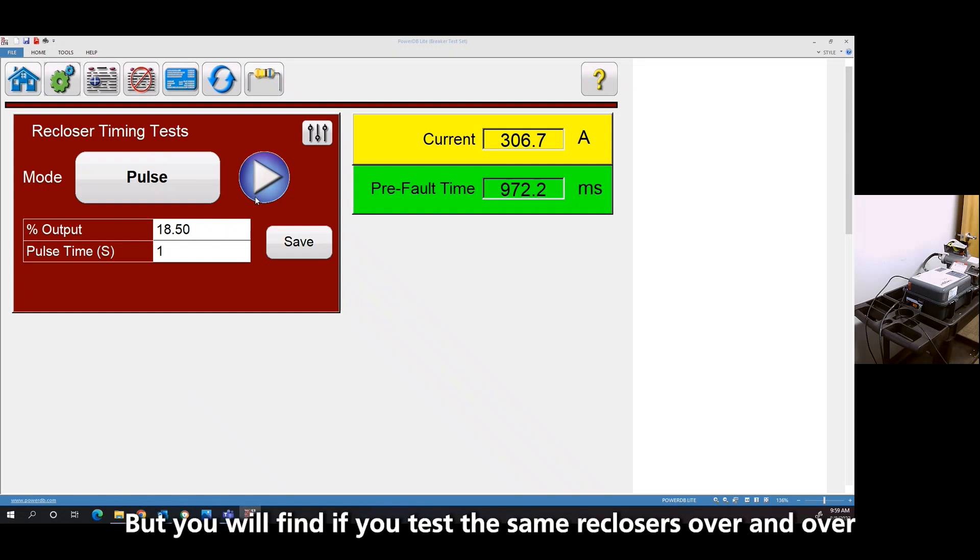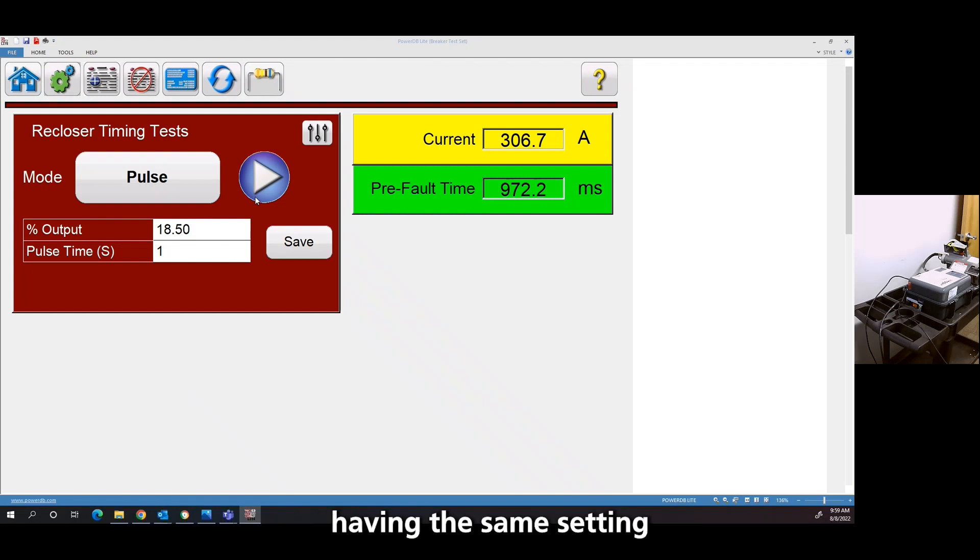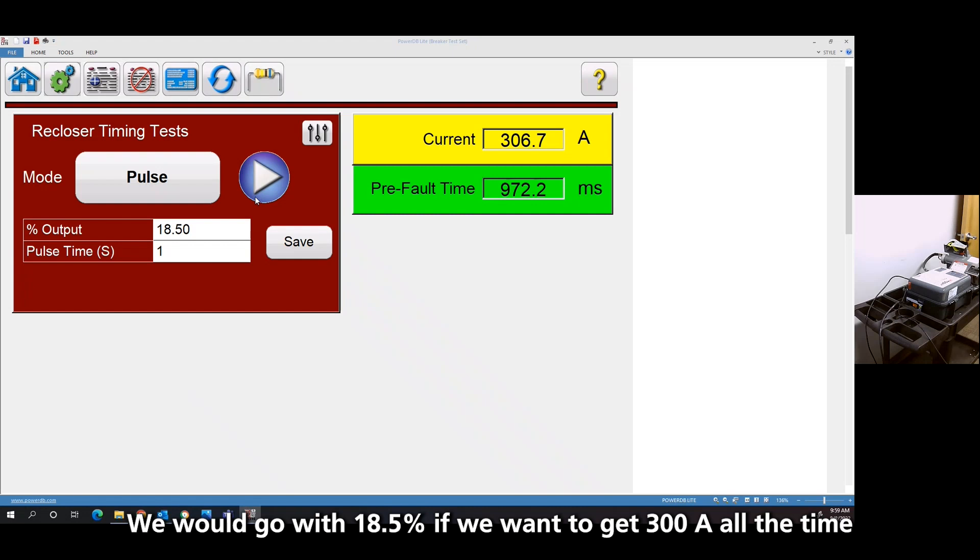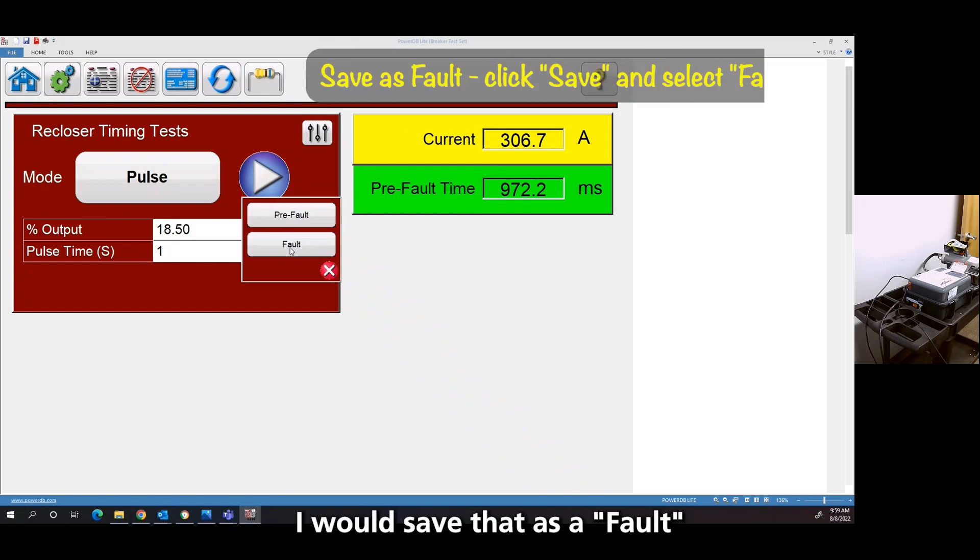The first time you have to kind of determine where your output needs to be to get the current you want. But you'll find if you test the same reclosers over and over at the same settings, it becomes pretty standard. We're going to go 18.5 if we want 300 amps. So I'm going to save that as the fault.